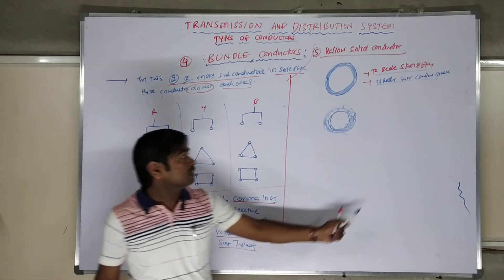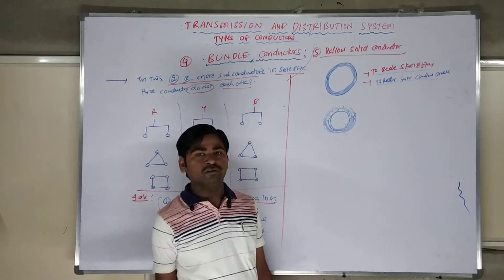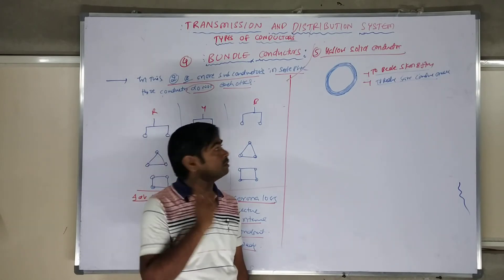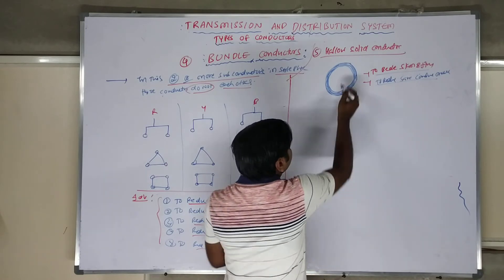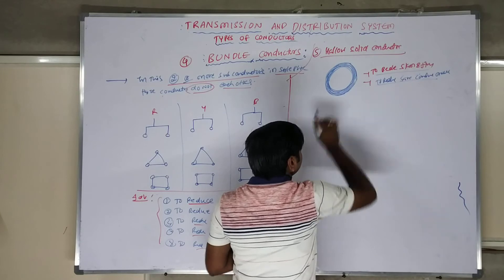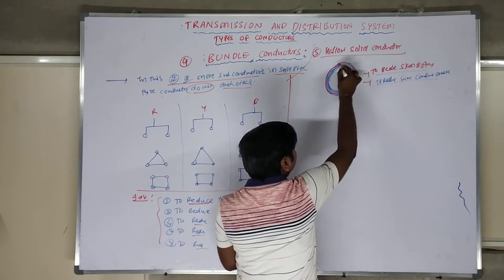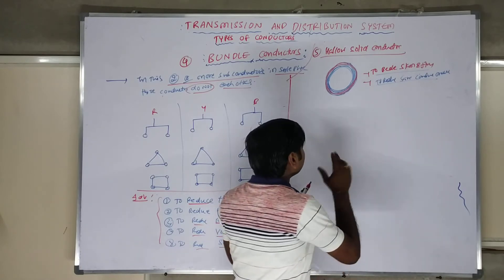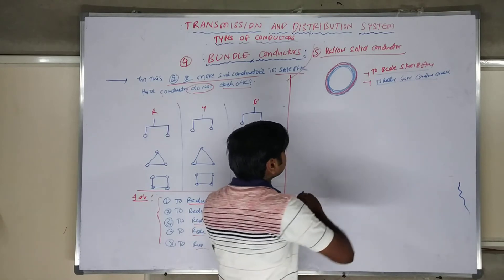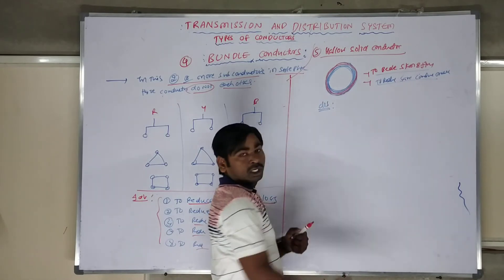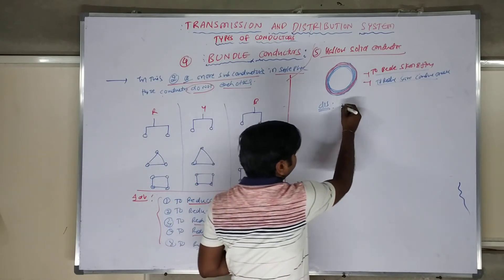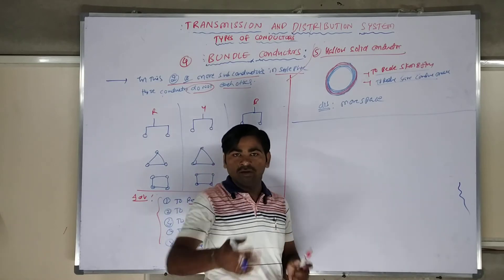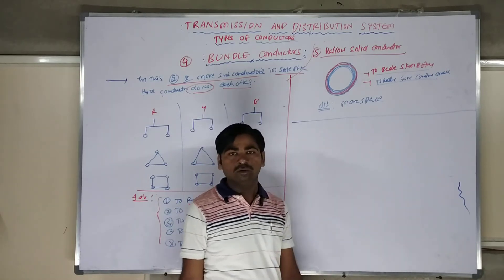The advantage of hollow solid conductor is to save conductor material and reduce the skin effect to a certain extent. However, even with a hollow solid conductor, the skin effect is not fully eliminated — it is not up to the mark. There is still some skin effect. Also, a drawback is that it will occupy more space and more cross-sectional area, meaning larger line supporters are required for R-phase, Y-phase, and B-phase. This is the problem with hollow solid conductors.